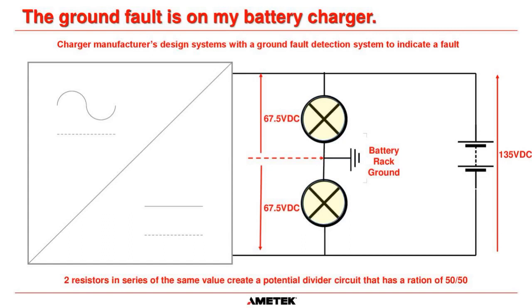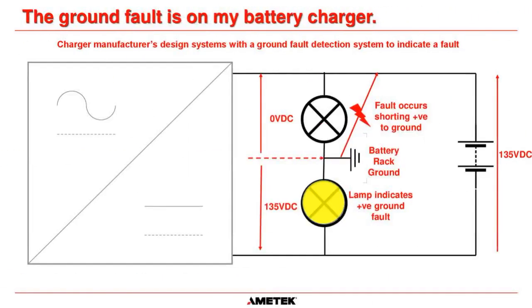Okay. And then if we do have a ground fault, so the positive here has faulted to ground externally somewhere, then the potential across this lamp now, because we have taken a direct short across that lamp, is now 0. And now all the potential is across this bottom lamp. So that bottom lamp shines really, really bright. And that would indicate that you have a positive ground fault. Okay, positive has shorted to ground. So that makes this point here 135 volts, and this point here is 0. So the full potential is across that lamp there, and the lamp will light bright and tell you that you have a ground fault.